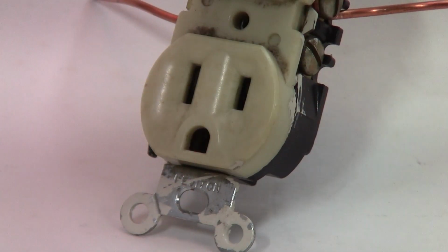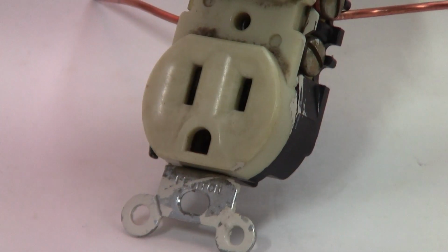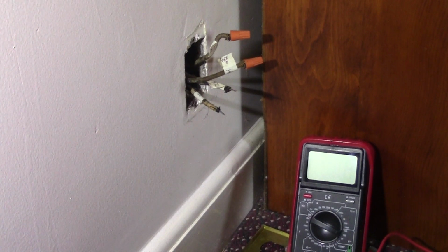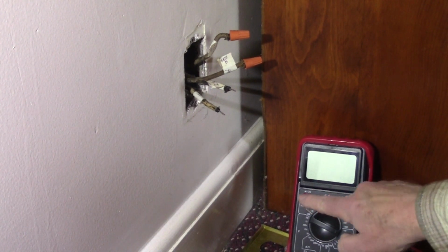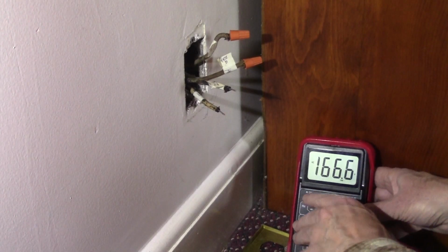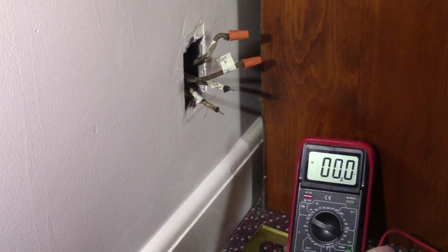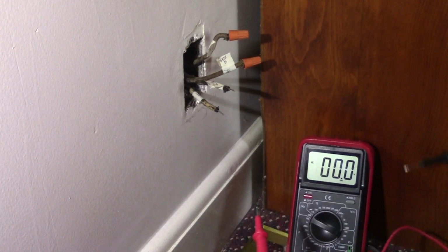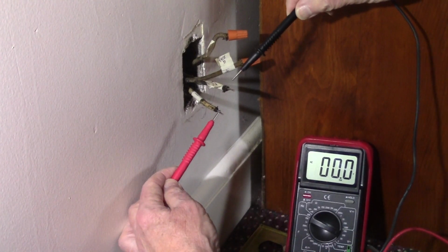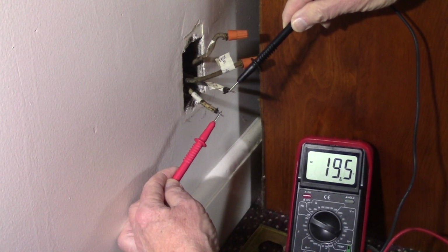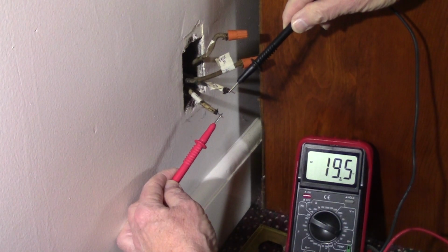Let's say you're replacing an old outlet, have flipped the circuit breaker, and are making a quick check to make sure the circuit is off. But instead of seeing zero in the DVM, you see a voltage, not line voltage, but definitely not zero. Is it really there, or does it just appear to be there when you connect the DVM? Should you be concerned? You shouldn't be concerned.